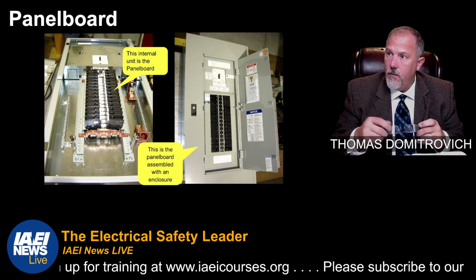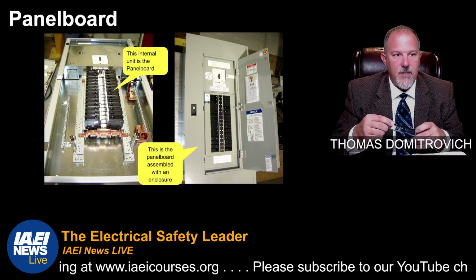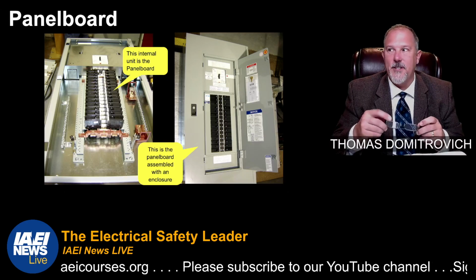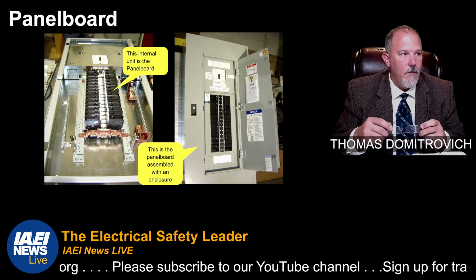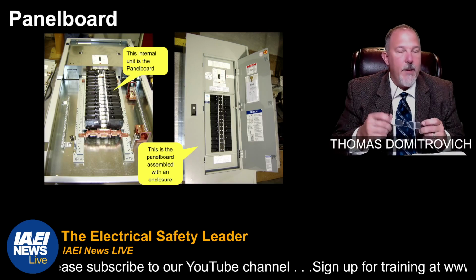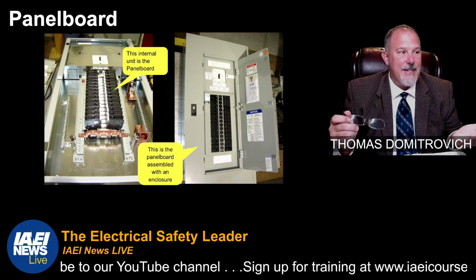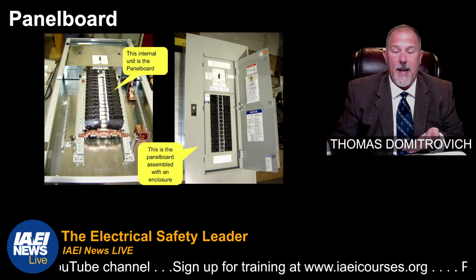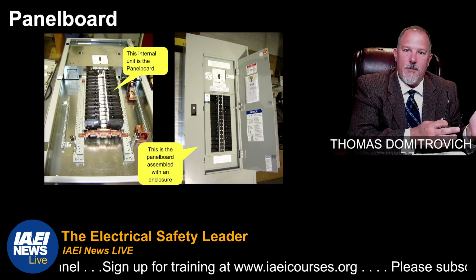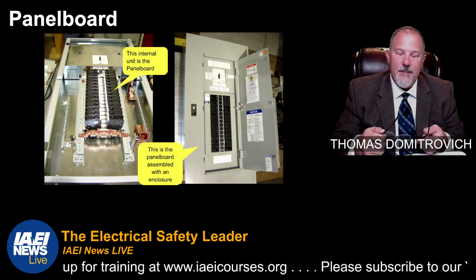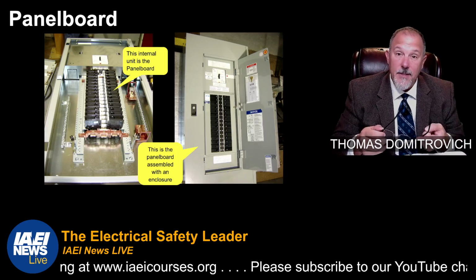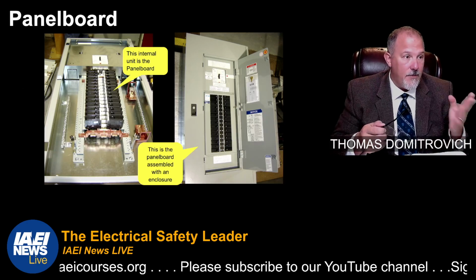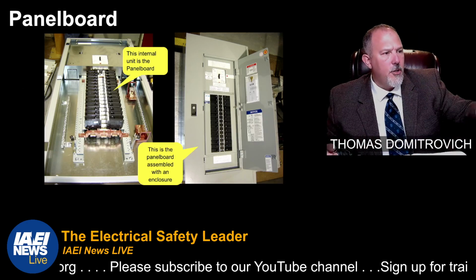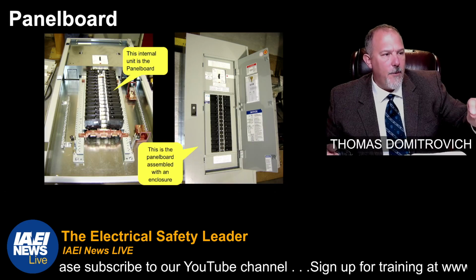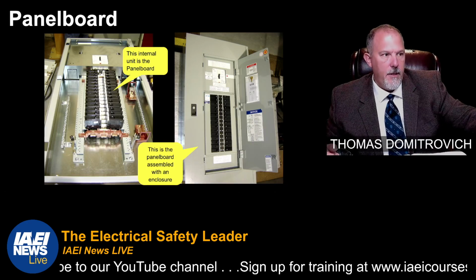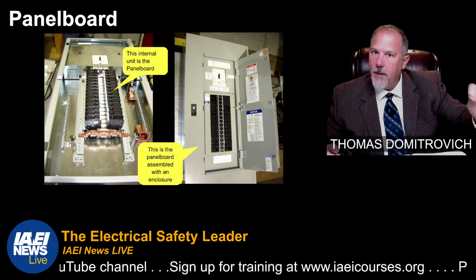I would say that's probably some vague language, because if the available fault current is less than 10,000, you still have to evaluate it for the application, just not in regard to available fault current. You still have to make sure the enclosure is listed for the environment. That does not cover there. The panel board enclosure combination shall be evaluated for the application. That's a pretty broad statement.